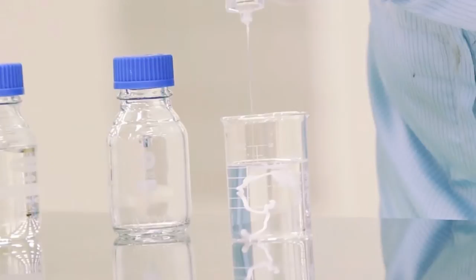When a solution of inner liquid is mixed with a spinning solution, the fiber gets formed. This process takes place inside the machines and the fibers are extruded. Nipro's unique polynephron membrane has an optimized asymmetric structure and wall thickness, which improves the mechanical strength of the fibers, reducing the risk of fiber leakage and providing better contact between the dialysate and blood components.